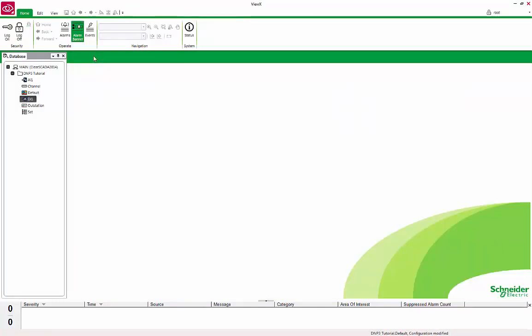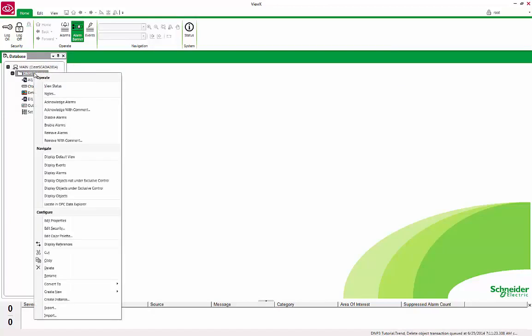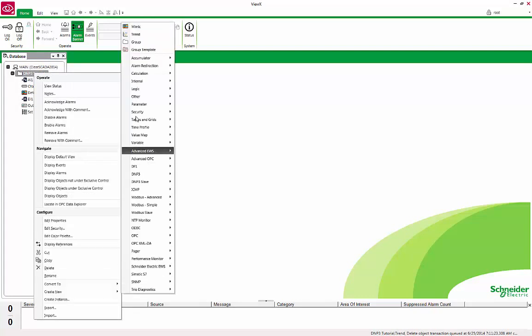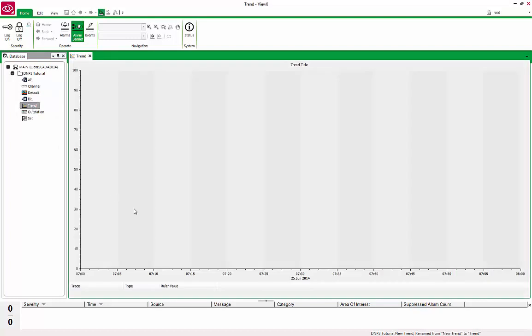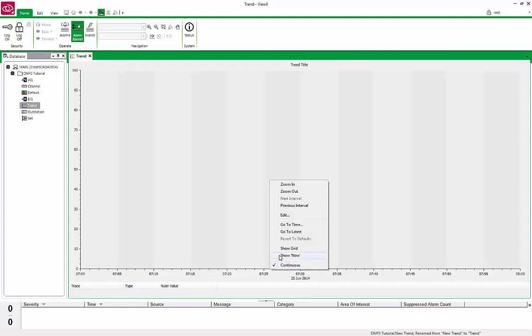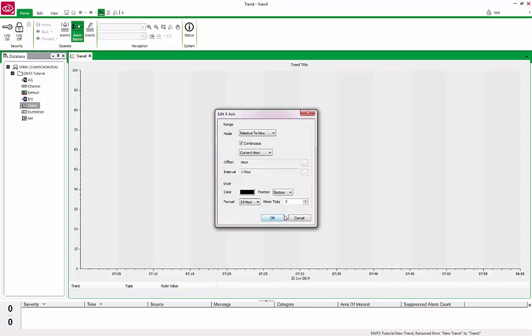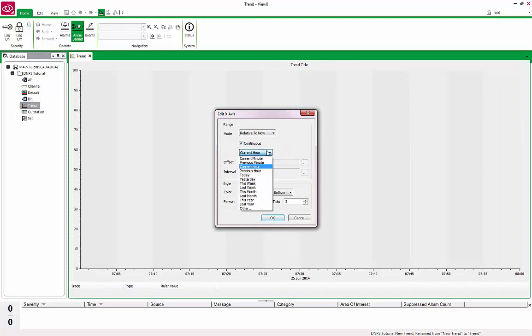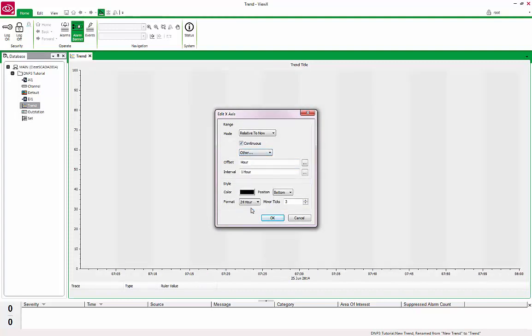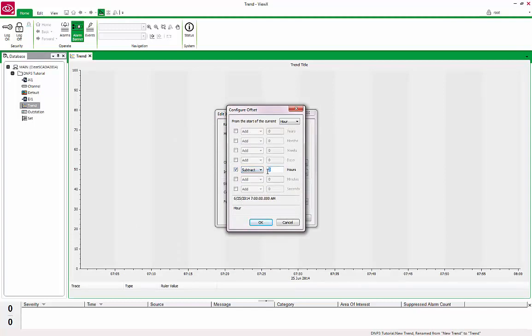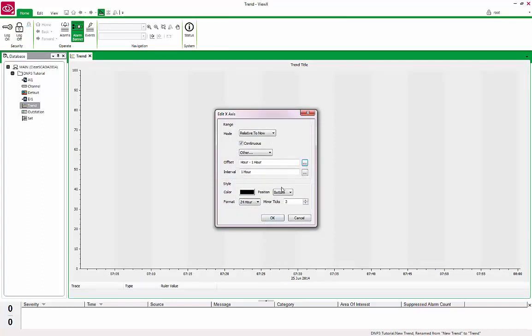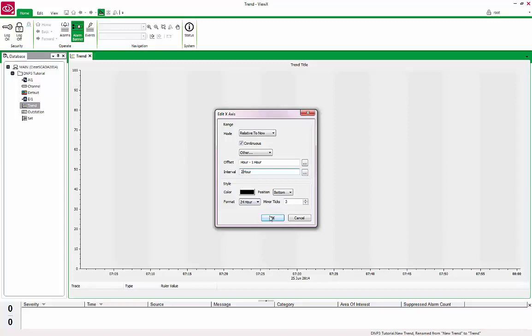We will now display the values on a Trend. Right-click on the DNP3 tutorial group, Create New, Trend. Rename it to Trend. Double-click Trend to open it in Design Mode. Right-click anywhere on the X time axis and select Edit from the menu. In the Edit X axis screen, under Mode, change the current hour to Other. For the offset, click on the Browse option. Click on the Hours checkbox. Select Subtract from the dropdown and enter a 1. Click OK. You should have Hour minus 1 hour in the offset entry. For Interval, change the 1 to 2.